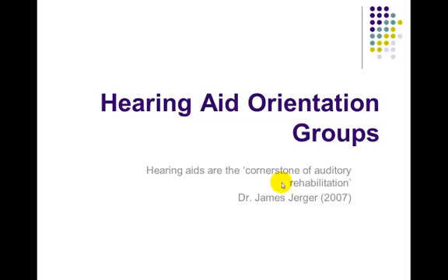Because remember, the equipment, based on the audiogram that you enter into the computer, is setting targets within the long-term average speech spectrum. So we want to make sure that soft sound is audible. If we present the carrot story at a soft volume, is it audible? Then we present the carrot story again, maybe first at 50 dB and then again at 65 or 70 dB, and then we're going to also present sound at a loud level to make sure it doesn't exceed their uncomfortable listening levels.